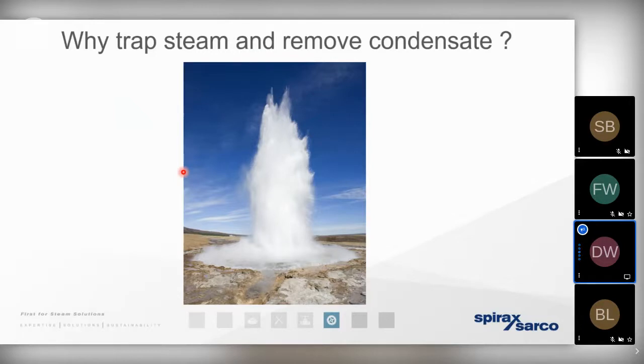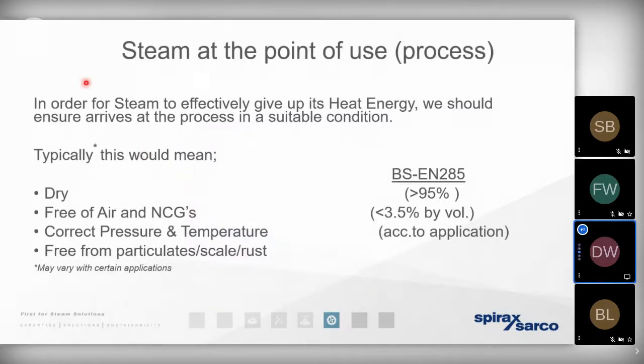So one thing that is worth mentioning is that different processes are going to use steam for different applications and for different purposes. So typically, when we're talking about a general traditional steam system that may be used on a closed loop heat exchanger, well, we know the benefits of keeping that steam as dry as possible, more energy in it, and there's less likelihood of mechanical damage.